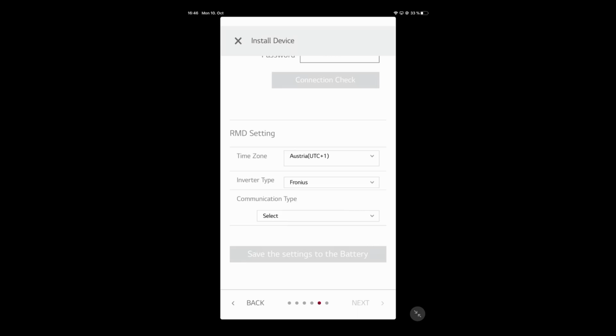And then for the communication type, we now want to set the termination resistance for the battery system. Since we install the battery system with the LG battery at the endpoint, so in this case with the termination resistance on at the battery system, we are now selecting here CAN RS485 terminal resistor to on position.